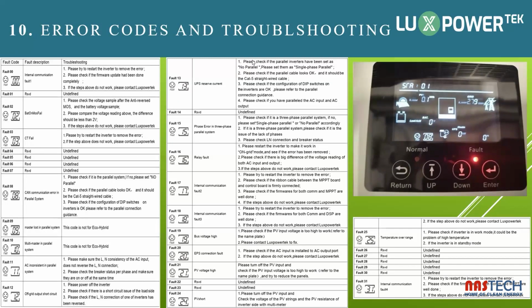There can also be an abnormal weather pattern on the roof, or there can be cables that are not well connected on the PV. And then obviously the other reason is if panels were connected to the inverter and it was not programmed beforehand. Also, some clients could mess up the programming and change those settings, and then immediately a fault occurs. So there's a number of reasons it can be. I hope that answered your question.